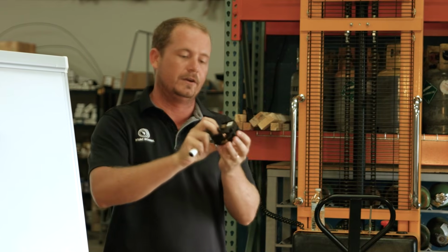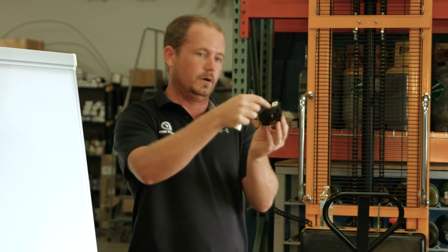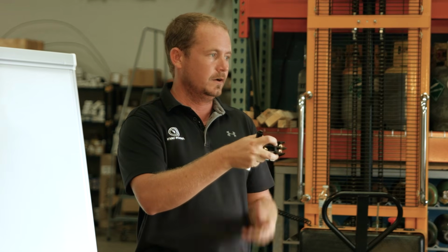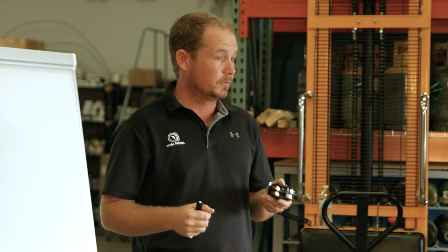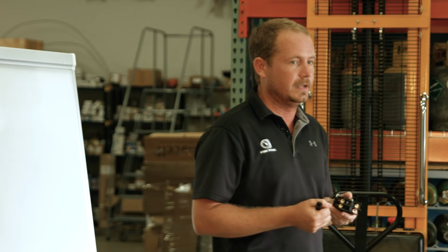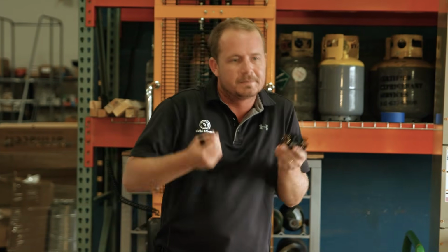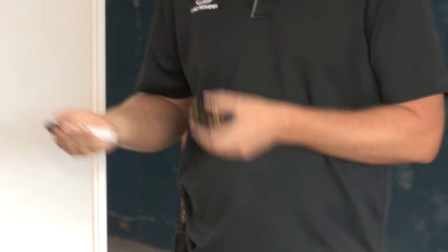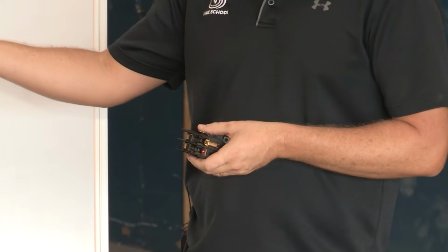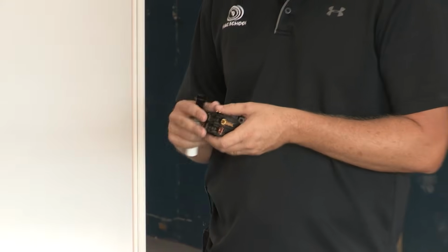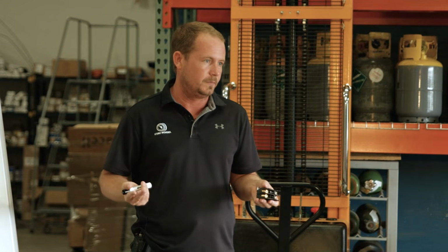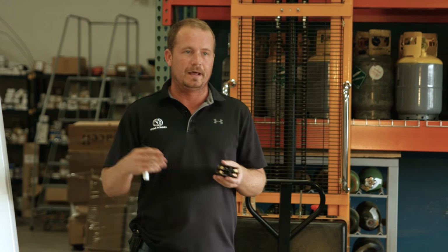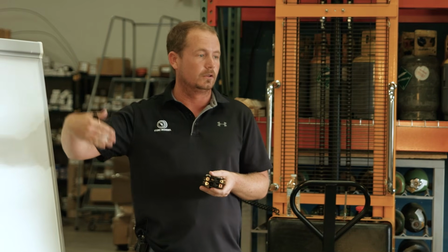Well, Y energizes our contactor coil, which is an electromagnet, which then pulls in our contacts, which then allows our compressor and generally our condenser fan to run. So it's a much more complicated story than just saying it's cooling. Now, if this were a straight cool unit, typical gas furnace or a system that just has electric heat strips, that would be all that cooling would be. You just energize that and your outdoor unit runs. Depending on how the system's set up, you may also need a G call in order to run your blower, but that's basically it.